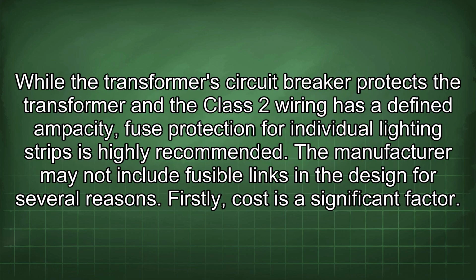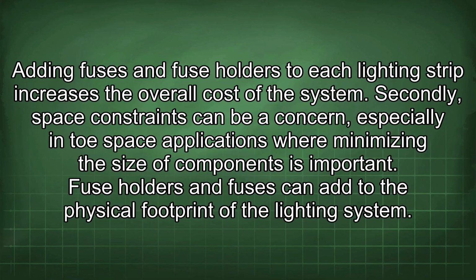While the transformer's circuit breaker protects the transformer and the Class 2 wiring has a defined ampacity, fuse protection for individual lighting strips is highly recommended. The manufacturer may not include fusible links in the design for several reasons. Firstly, cost is a significant factor. Adding fuses and fuse holders to each lighting strip increases the overall cost of the system.